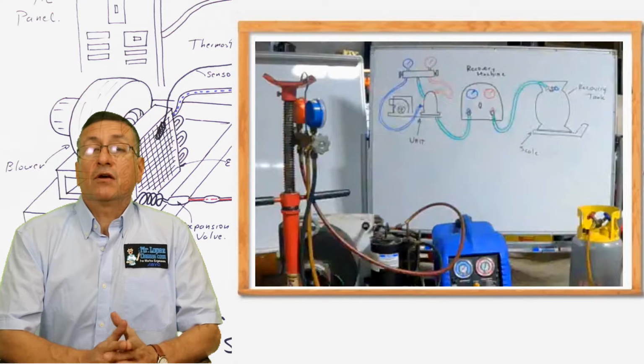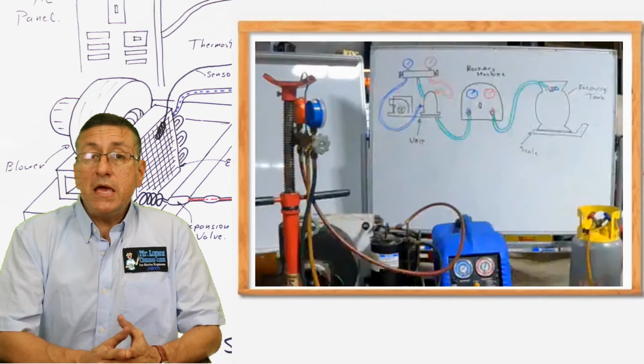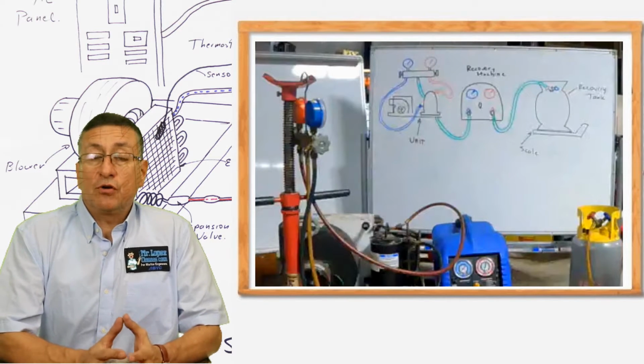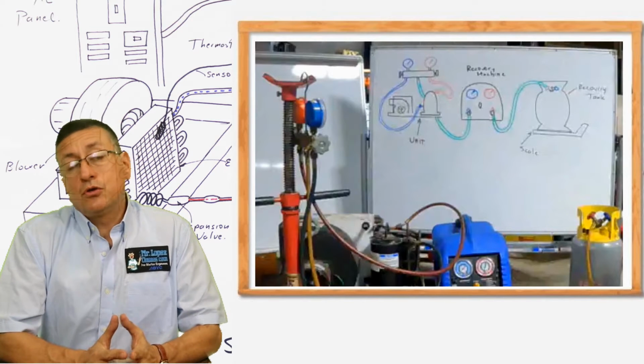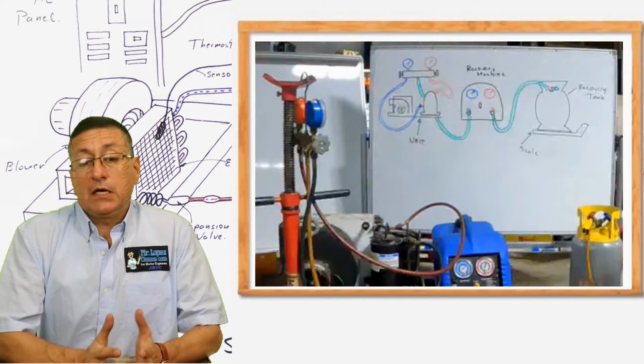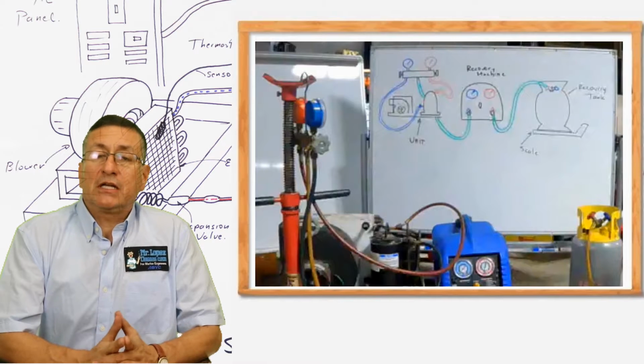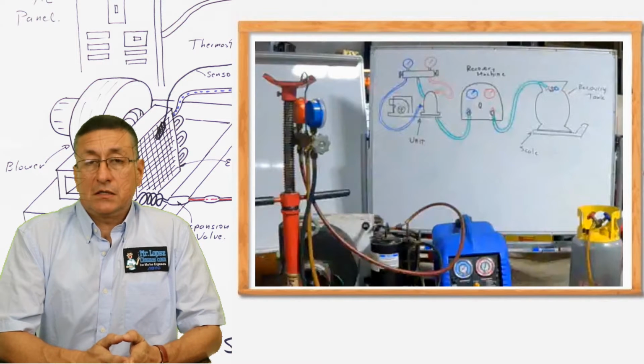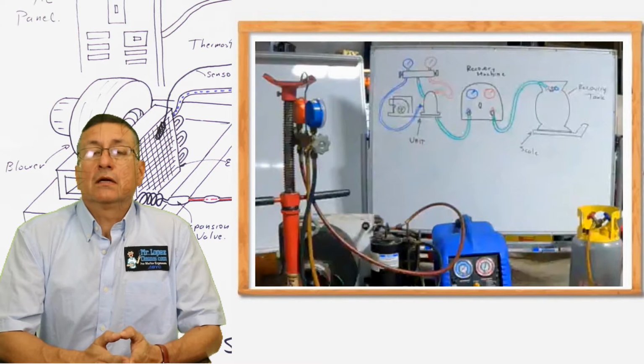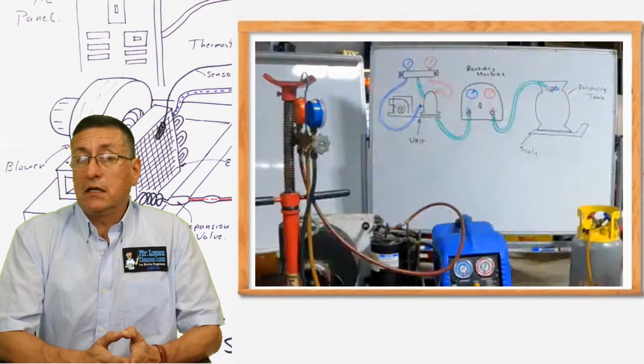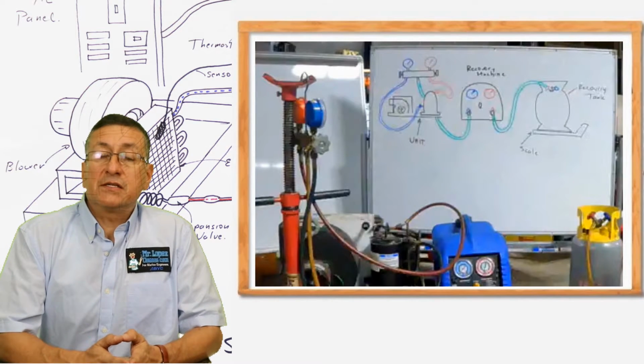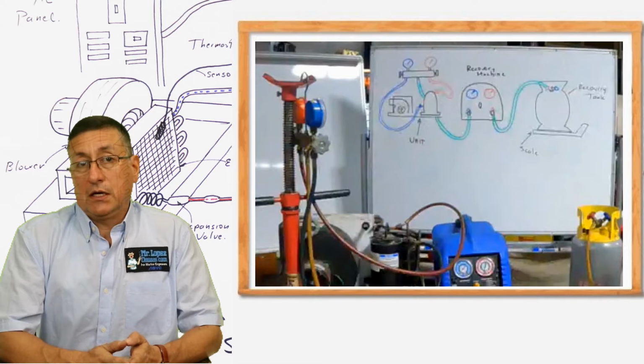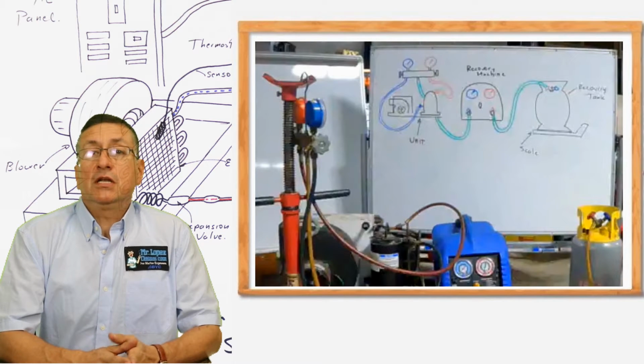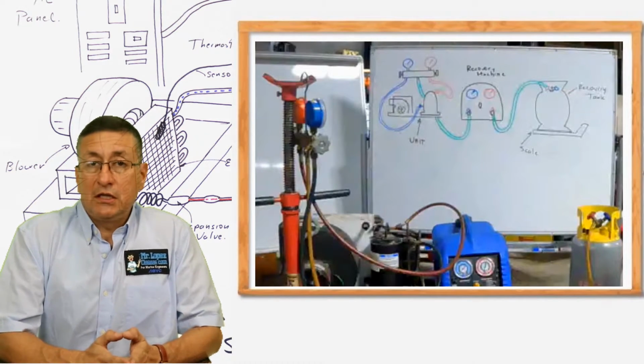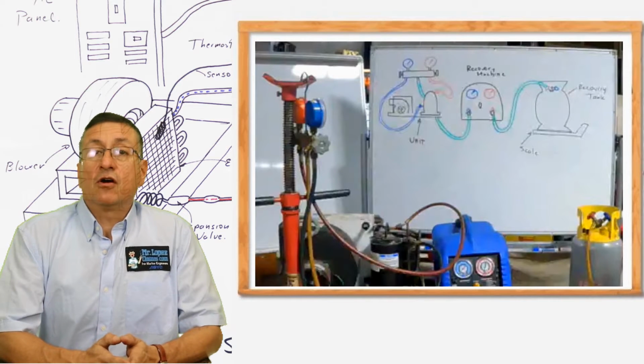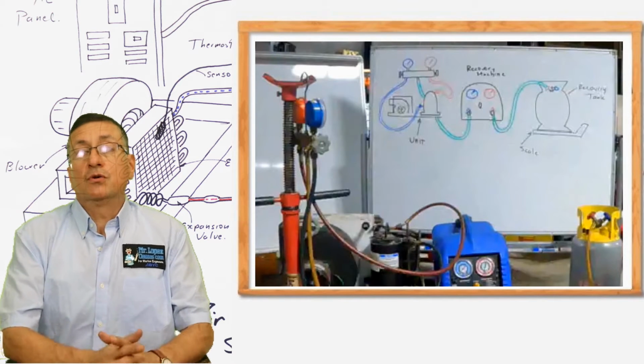It's important to recover the refrigerant in the proper way in order to avoid damage to the compressor of the equipment and also damage to the recovery machine. For that reason, the selection of the tank to recover the refrigerant is important. There are specific tanks according to the refrigerant, and the recovery machine is a vital component in this process, especially in the recovery procedure.